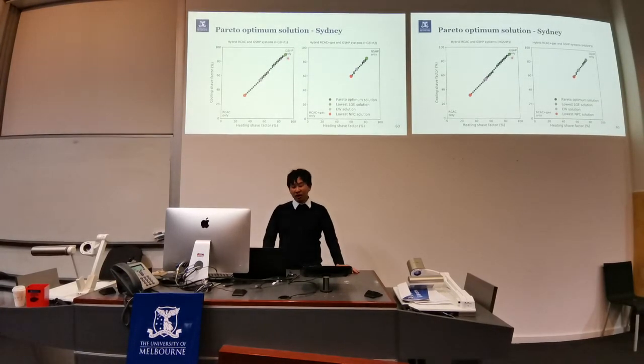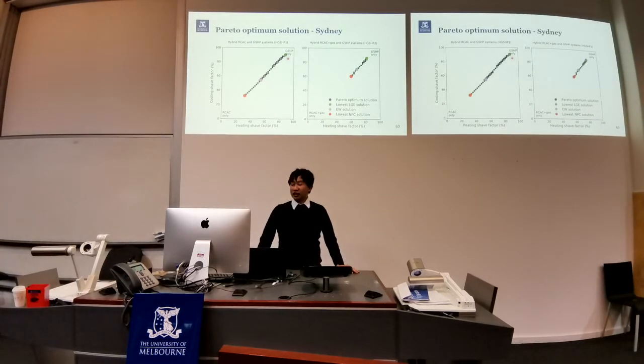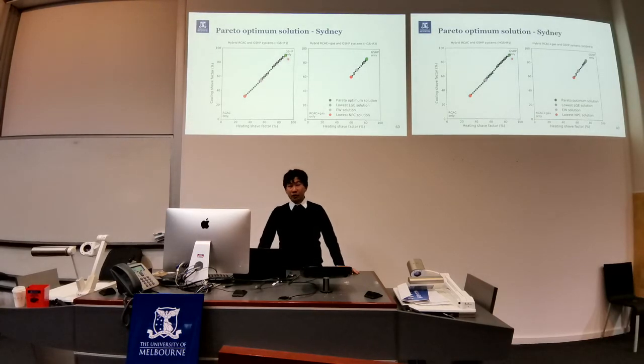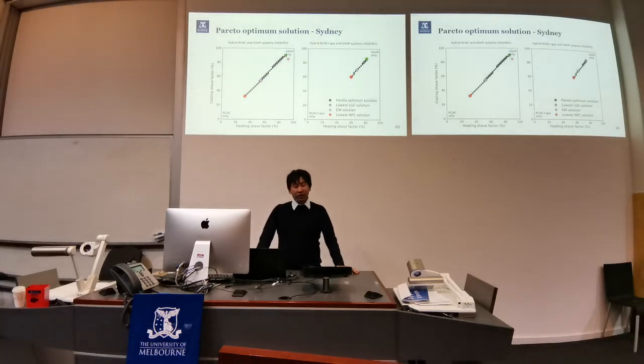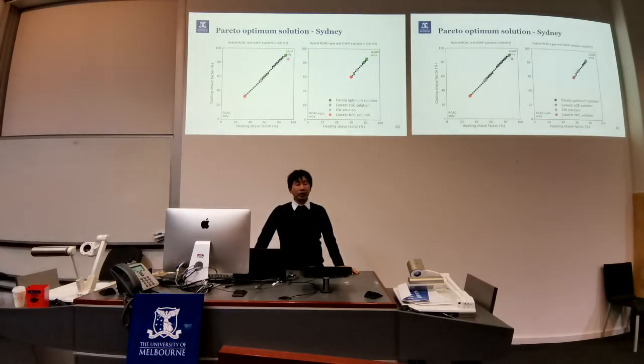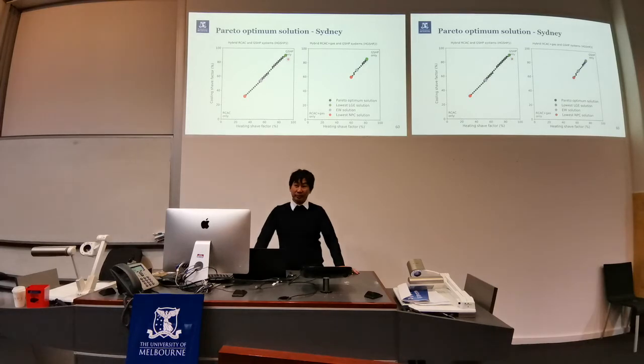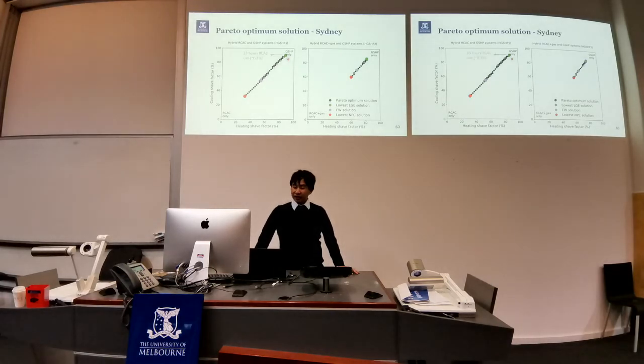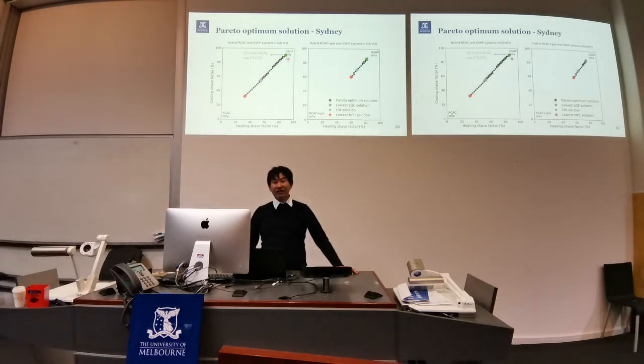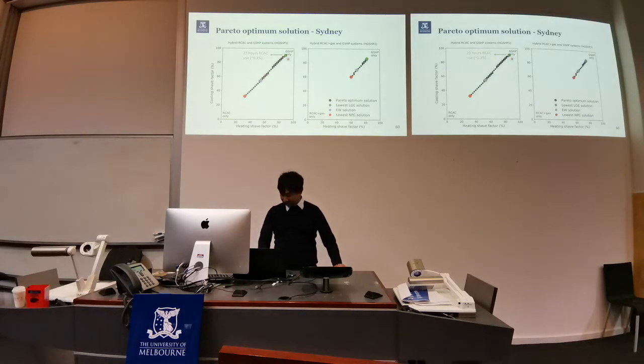Installing a slightly smaller ground source heat pump at this point results in a lower ground heat exchanger requirement. That means lower emissions generated through the drilling process. So at this point, the ground source heat pump system is sized to meet 90% of the peak load. In fact, the ground source heat pump is able to meet 99% of the thermal demand. The less efficient air conditioner is only used for 1 day in a year.